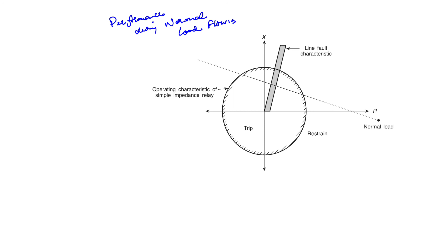Now let us discuss the effect of arc resistance on the reach of the simple impedance relay. Let us consider a fault with the fault resistance. We will have the fault resistance, that is R arc, at this point C in a single line diagram. Now the impedance seen by the relay lies on the boundary between the trip and the restraining region, and thus any arcing fault just beyond C will not be detected. So you will see that this is C, and in this case CR is actually the arcing resistance.